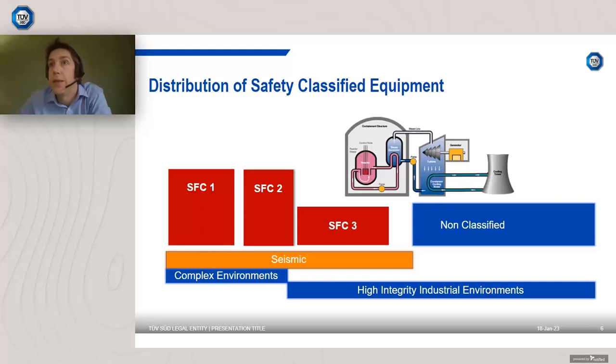All equipment that does require certification or qualification — seismic, shown in orange — has an almost universal baseline requirement, but increasingly this is addressed by analysis. We've had EQ files certifying seismic performance by analysis accepted on nuclear new builds within the last couple of years. Seismic requirements are not necessarily expensive or time-consuming to address. Most challenging nuclear accident conditions only apply to a fraction of components primarily located within containment. For most equipment, qualification is probably less demanding in functional terms than you may think.